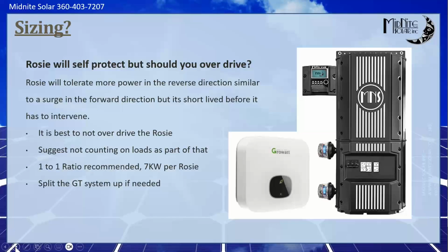So what does happen if something causes the grid tie inverter to exceed the Rosie's rating? So you'll hear, this is where we're going to talk about one-to-one ratios and GT to battery-based inverter sizing ratios. Some inverters, if you exceed the limit, the inverter will break. Some inverters can regulate. SMA Sunny Island was really good at regulating and not being damaged.